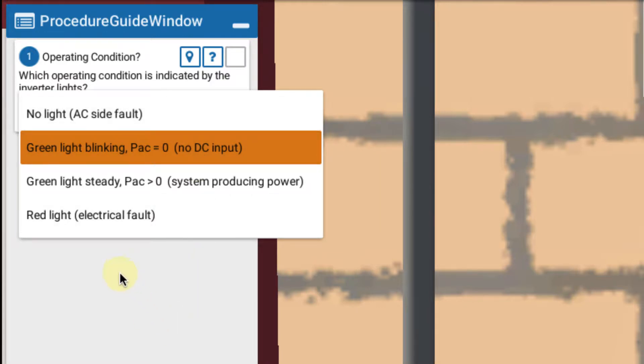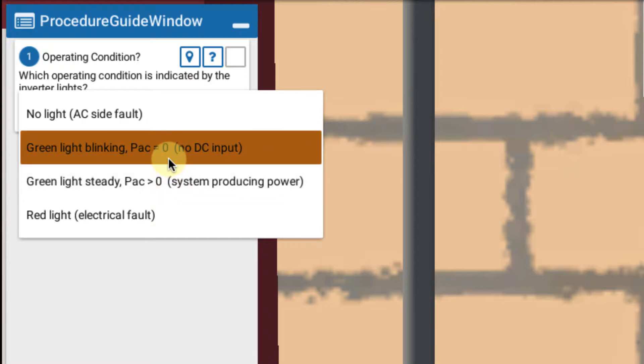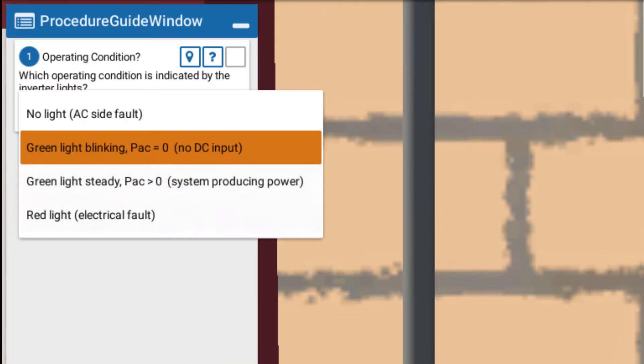...with power AC equals zero. That indicates no DC input from the array. A green steady light with power AC greater than zero. That indicates the system is producing power. And then a red light indicating an electrical fault like a ground fault.